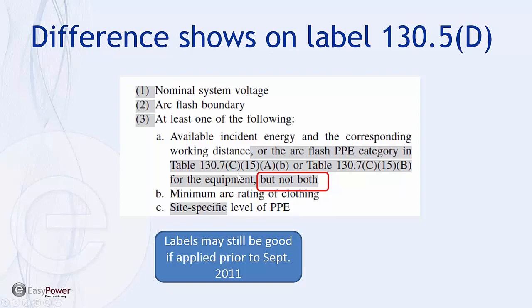So we've had questions when we do these discussions online about, well, all I need to do now is say, okay, the PPE category is category 1 or category 2. But in fact that's not allowed per this regulation, this particular article. If we're going to have incident energy and working distance, then we cannot put on the PPE category as referenced by these particular tables. Now, the way I read this is that my safety manual can determine specific site level categories if I define what those categories are, and I spell out what the PPE is for category 1 and category 2 and category 3, and I tell the worker that based upon this incident energy, you go to this category level as determined by company XYZ.